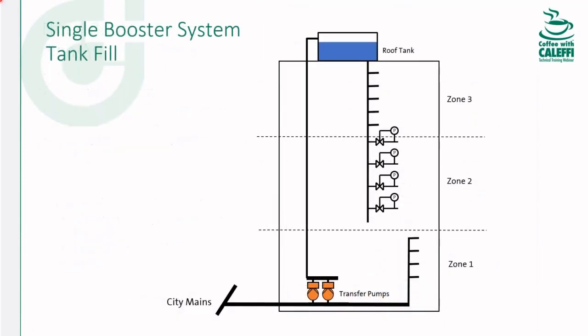Sure. Okay, so an interesting design here. The single booster with a tank fill. And I think this is used in New York. I'm not sure if they still do it. But basically you've got transfer pumps that boost all the way up to the tank on the roof, and ignore the symbol. You wouldn't really need VFDs for those pumps. Just size them correctly and they'll fill that tank. As long as you're running at the best efficiency point, that's what I would target.